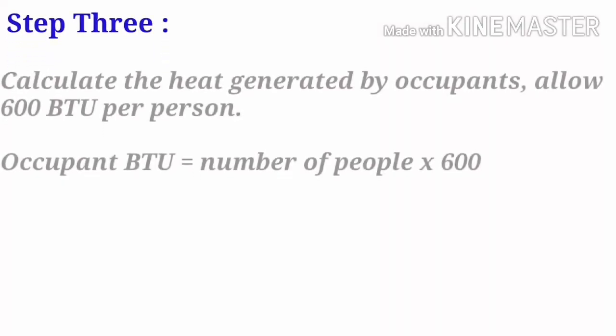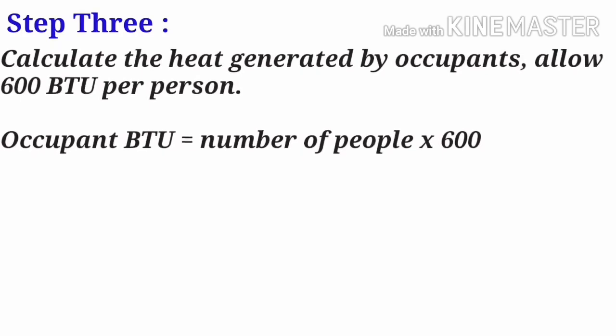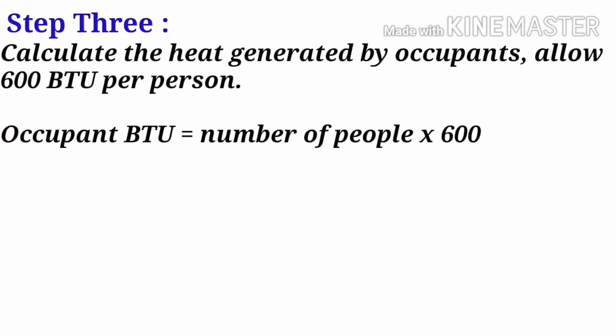Step 3: Calculate the heat generated by occupants. Allow 600 BTU per person. Occupant (BTU) equals number of people multiplied by 600.